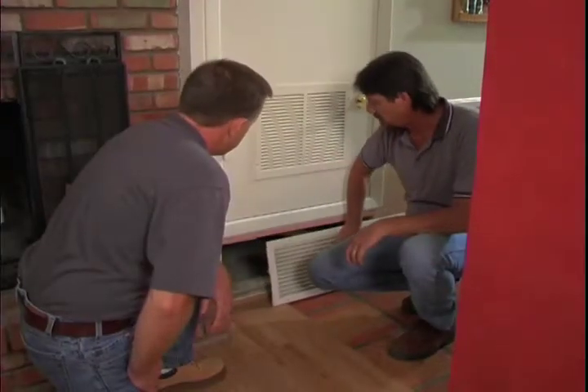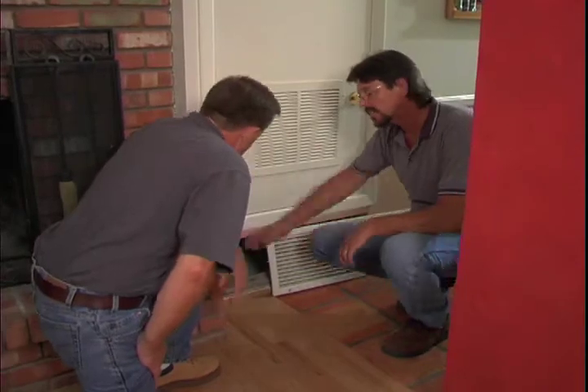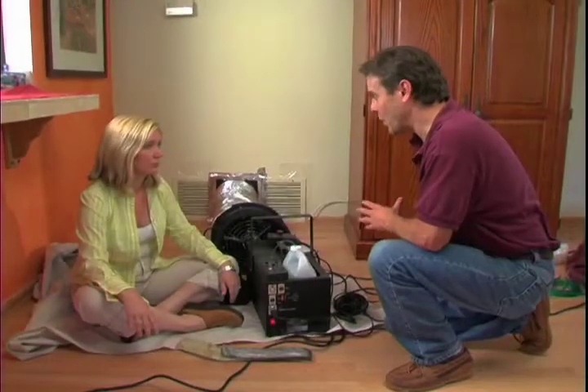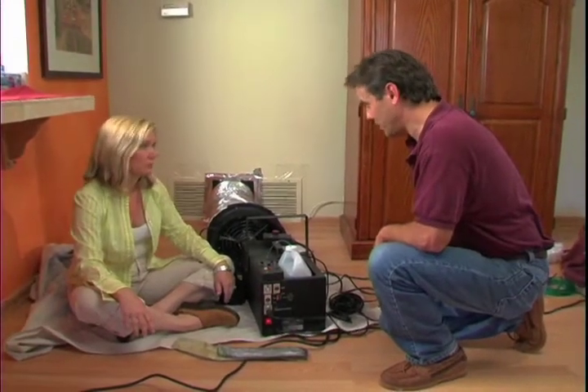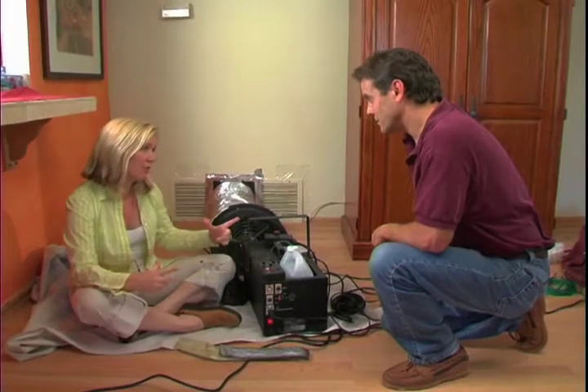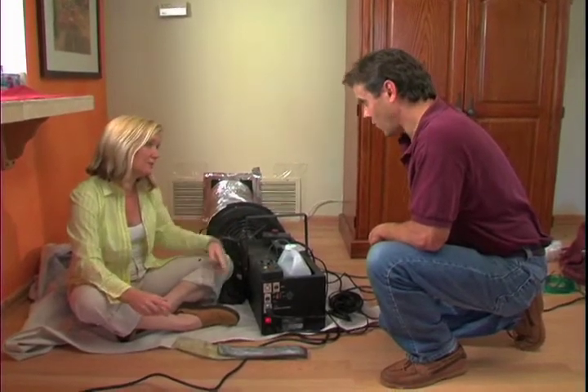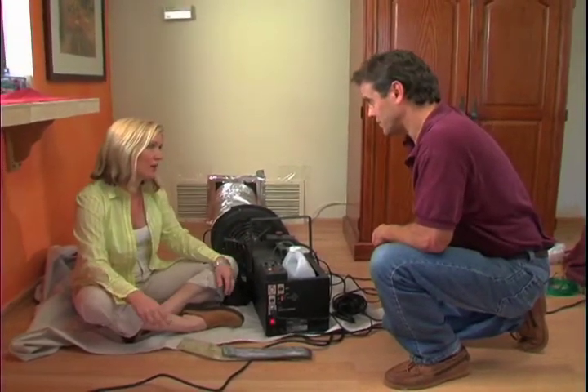I know Charlie and Ken found a big hole between the return air platform and the chimney too. Correct, it's a big hole, and that may be the main reason why we couldn't get an accurate reading with the duct blaster. Sounds like we should seal off those holes and then maybe retest the system. Right. How about if we go see if there are any other obvious leaks? Sounds like a plan.